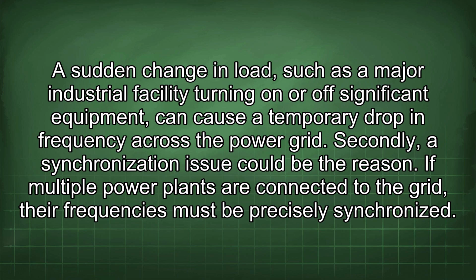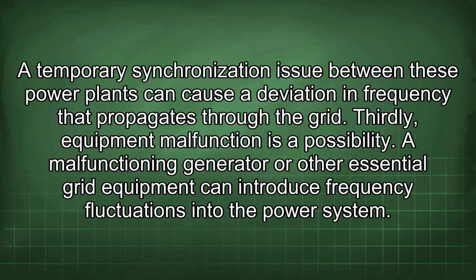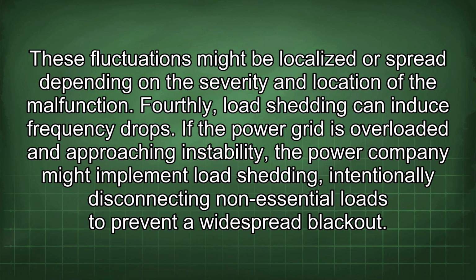Secondly, a synchronization issue could be the reason. If multiple power plants are connected to the grid, their frequencies must be precisely synchronized. A temporary synchronization issue between these power plants can cause a deviation in frequency that propagates through the grid. Thirdly, equipment malfunction is a possibility. A malfunctioning generator or other essential grid equipment can introduce frequency fluctuations into the power system. These fluctuations might be localized or spread depending on the severity and location of the malfunction.